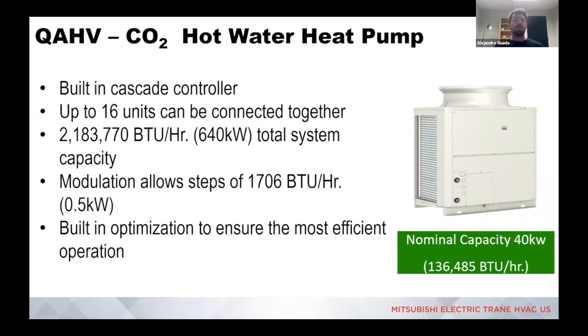Can you grab, if you have the storage tank and let's say you have some capacity limitations, can you grab heat from the tank and pull it back into your hydronic box to provide space heating in some instance, like a very cold night in a low temperature ambient? Is that possible? Like you can put heat in the tank, but you can also pull heat out of the tank for space heating.